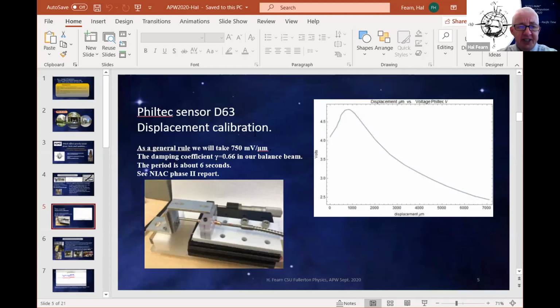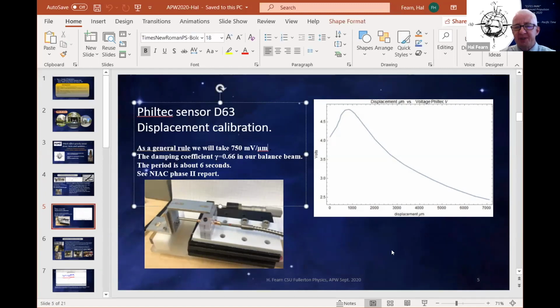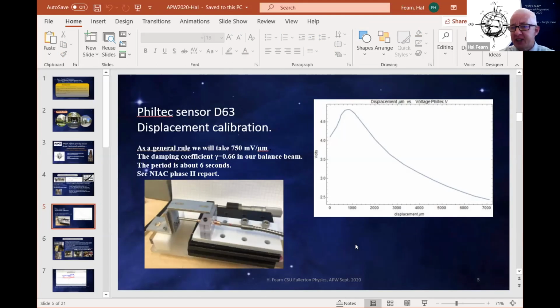I also took off the Philtec sensor. This is the Philtec sensor that we use, and I even took off the metal bracket here, which has a shiny piece of tape on it, and you can't really see it, but it's got reflective tape on there. And I actually moved this thing back with a vernier scale to do the calibration, so using our own equipment, not just the calibration that was given to us by Philtec. So I managed to get a very accurate rule as 750 millivolts per micrometer for displacement. So not only can I give you the force very accurately, I can also give you the displacement very accurately. The period of our balance is about 6 seconds.